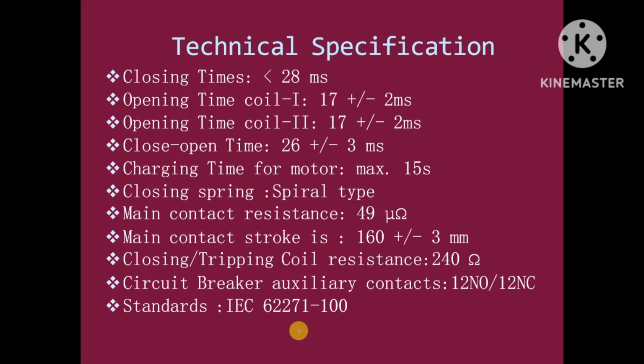So the technical specification of this particular breaker is: the closing time is 28 milliseconds and its opening time is nearly 17 plus minus 2 milliseconds. There will be 2 tripping coils and 1 closing coil, so closing will be less than 28 milliseconds and tripping or opening will be 17 plus minus 2 milliseconds. Close-open time is 26 plus minus 3 milliseconds. The spring charging motor will take 15 seconds to charge the closing spring. The closing spring is one more important point; it is spiral type. The main contact resistance is 49 micro ohm and the main contact stroke is 160 plus minus 3 mm. Closing and tripping coil resistance will be nearly 240 ohm, and there will be 12 NO and 12 NC auxiliary contacts provided, and it follows the IEC standard 62271-100.